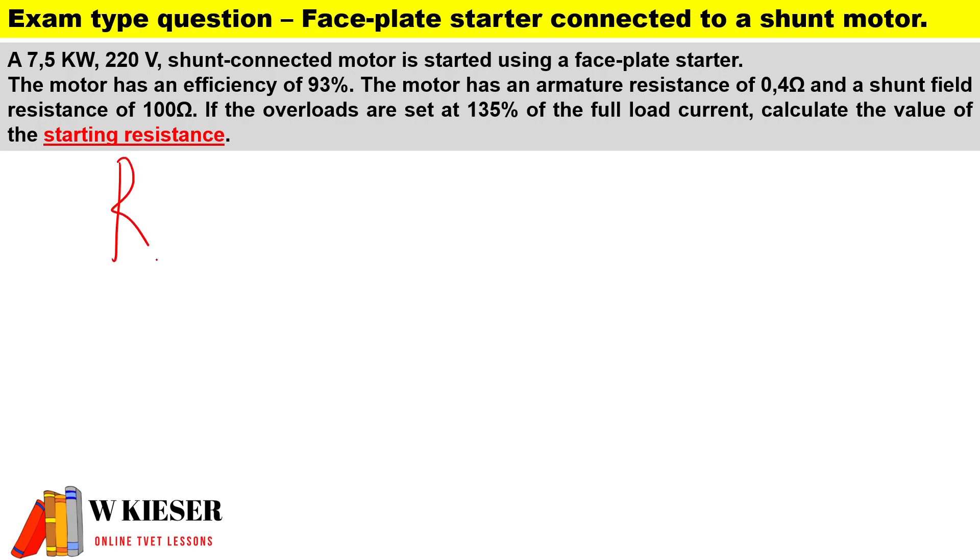To calculate R_start, it'll be the terminal voltage over I_a_max, so the maximum armature current that the armature will experience, minus R_a. We're going to have to calculate R_start using this formula.